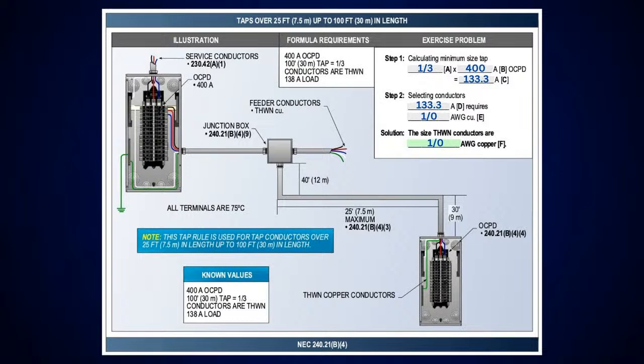In this one, you've got a 400 amp overcurrent device upstream. Take it at a third. That's 133.3 amps. I'm going to do it based on a copper conductor. Look in the 75-degree C column. A 1/0 is good for 150 amps, and you sized it. So that's the minimum. That means right here, based on this, I'd put a 150 in, and I could go up all the way to a 400 amp overcurrent device. But once you go to 400, it's no longer a tap.